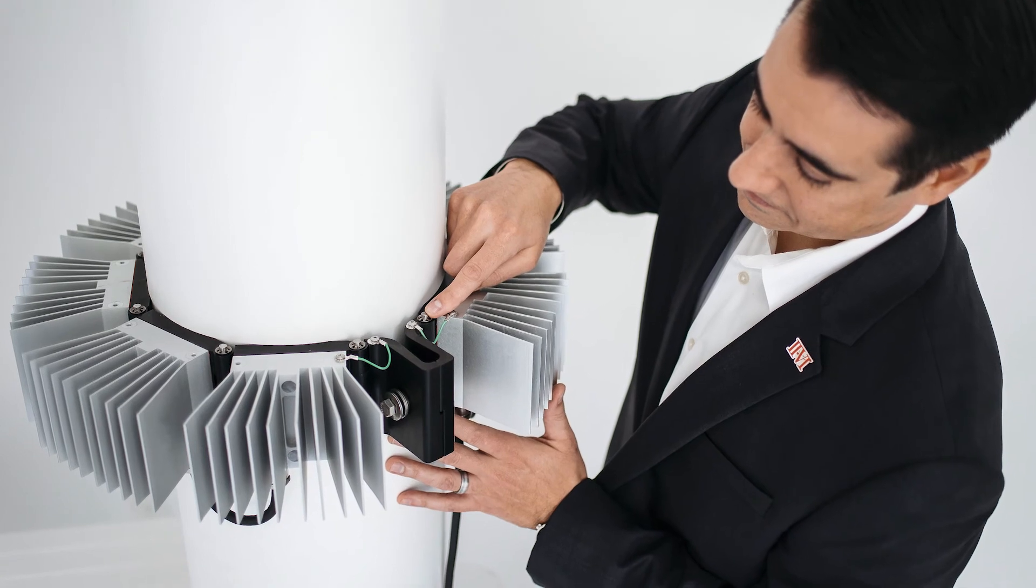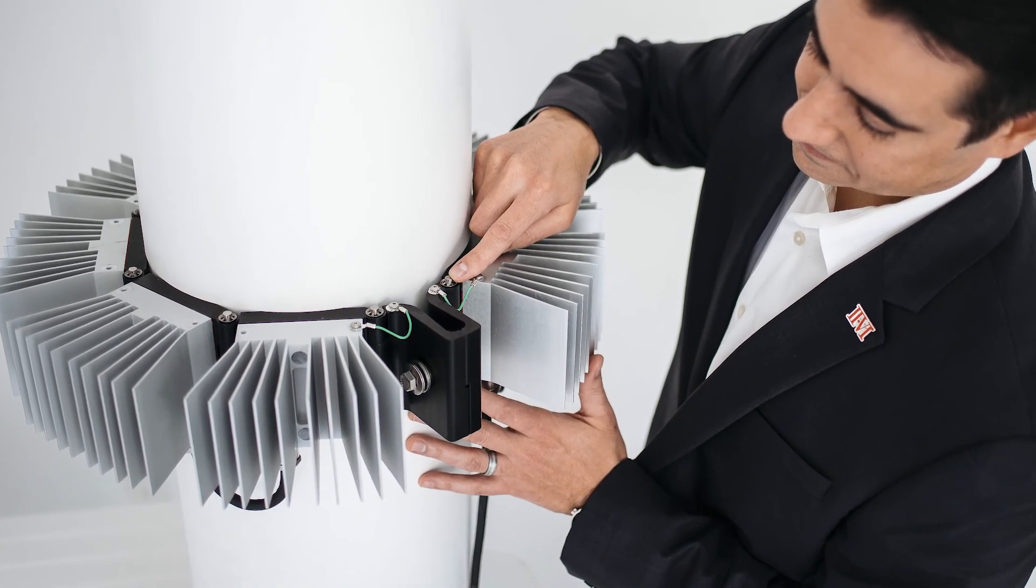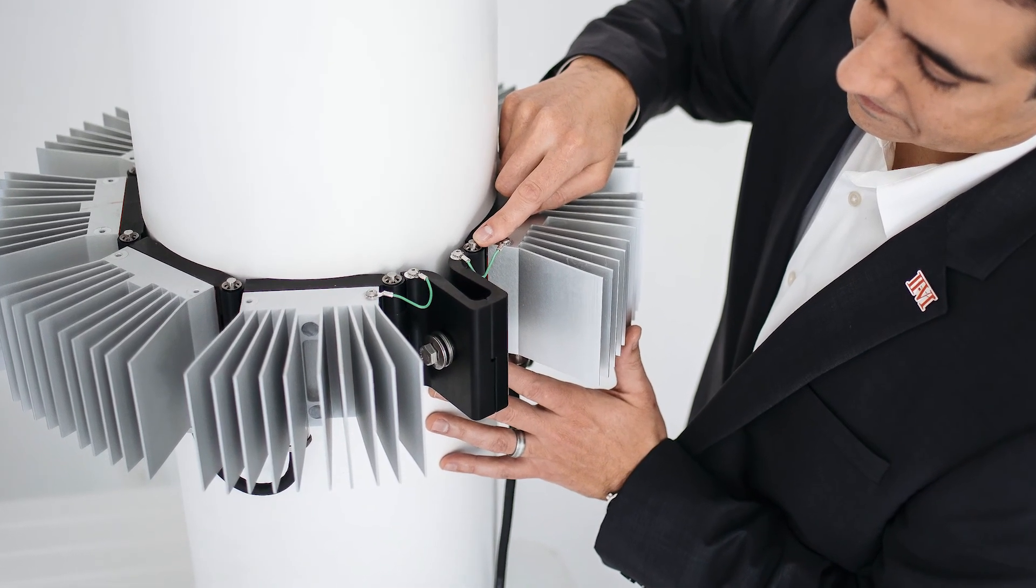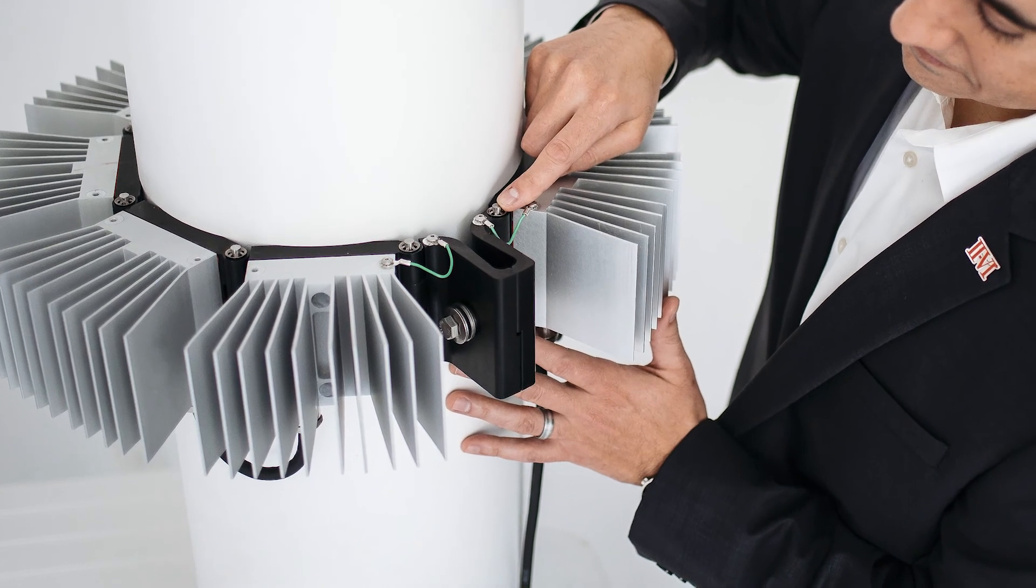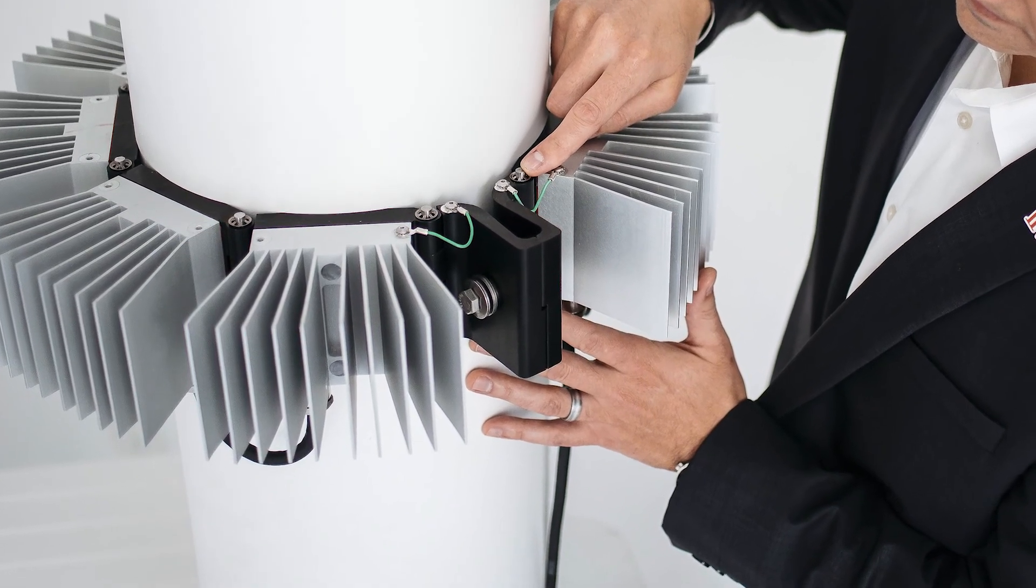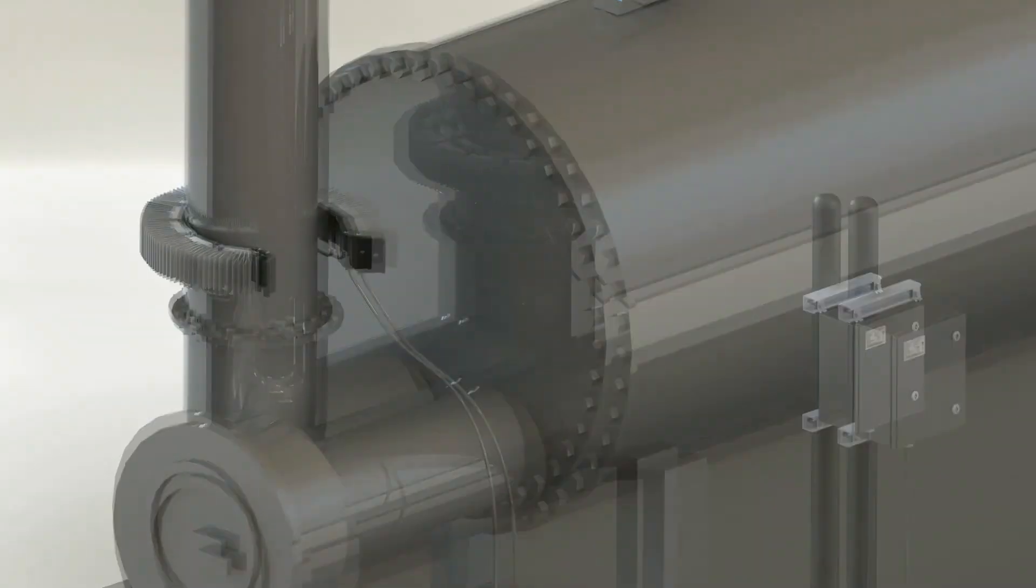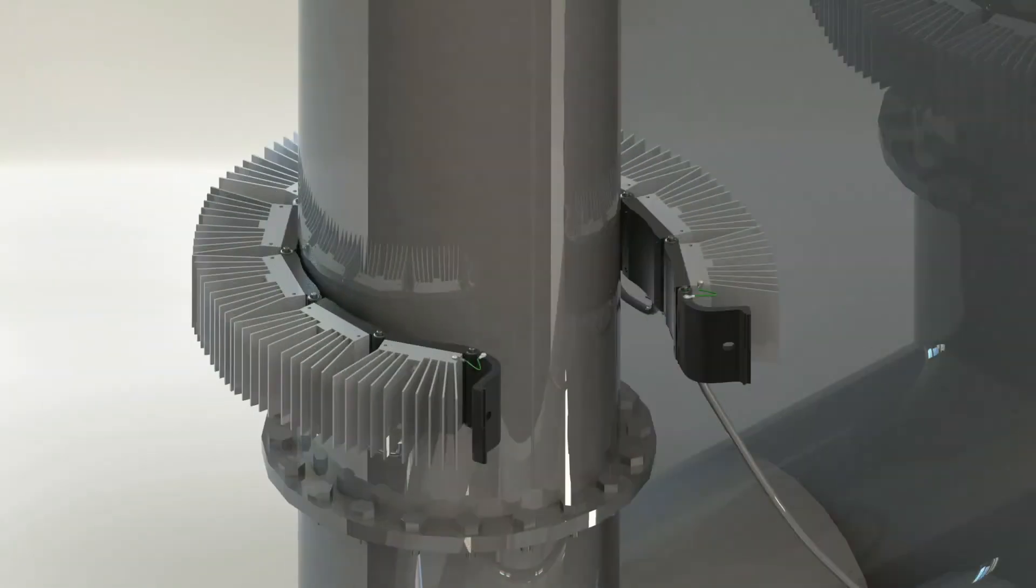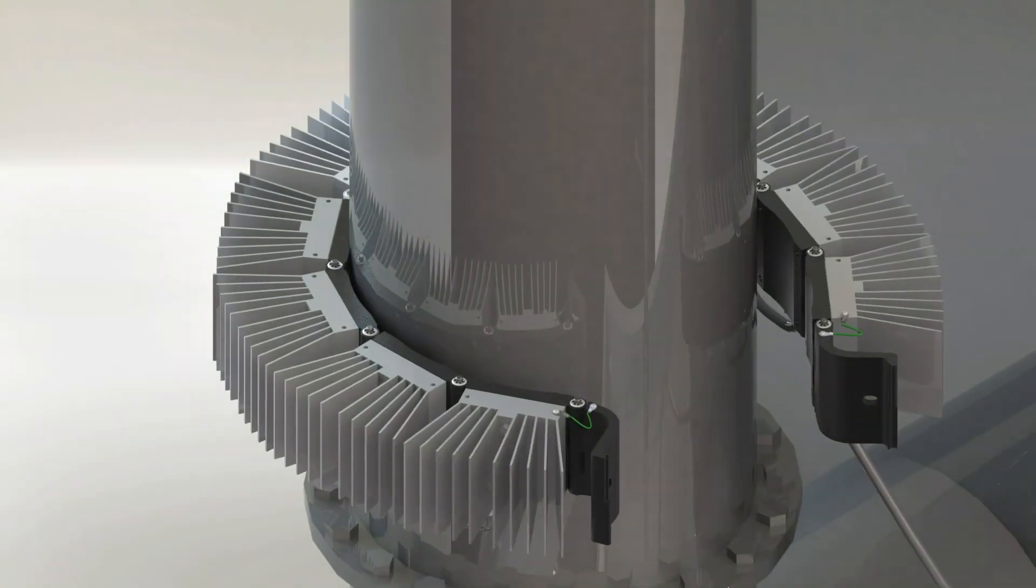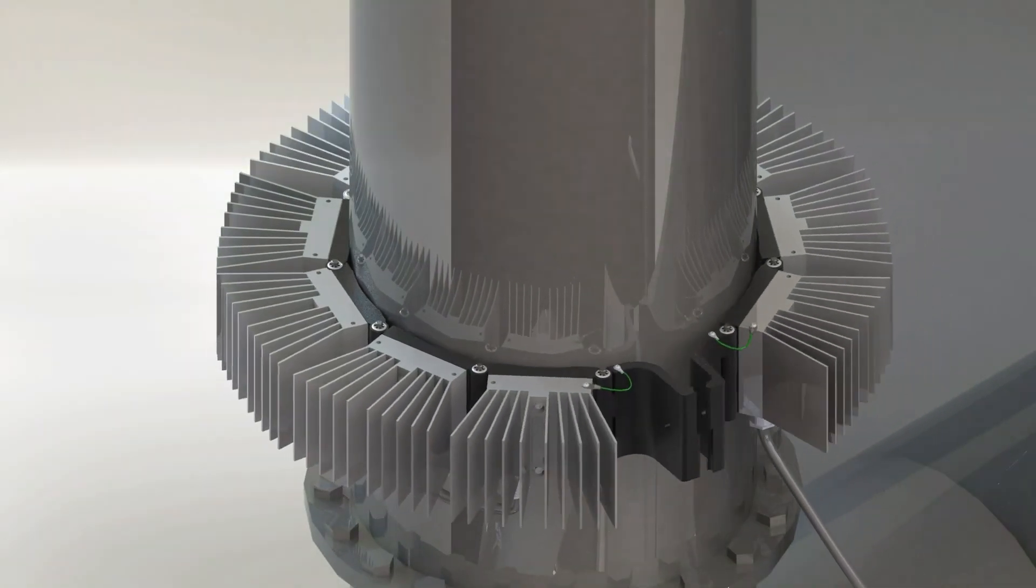Installation is simple. First, locate the portion of the exhaust stack with the desired operating temperature using a thermocouple wand or non-contact temperature reader. For maximum power production, this would be the section of the exhaust stack that reaches a maximum of 160 degrees Celsius.